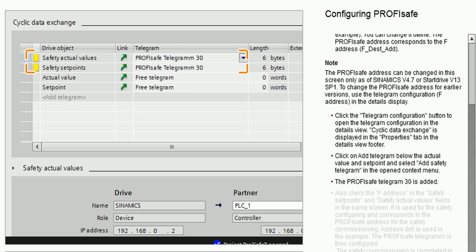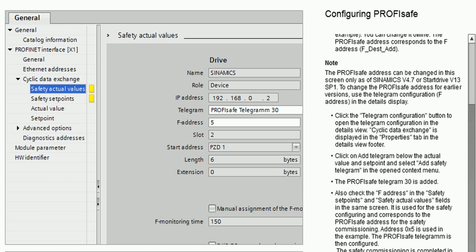The PROFIsafe Telegram 30 is added. Also check the F address in the Safety Setpoints and Safety Actual Values fields in the same screen. It is used for the safety configuring and corresponds to the PROFIsafe address for the safety commissioning. Address 5 is used in the example. The PROFIsafe Telegram is then configured. The safety commissioning is completed in the next step.